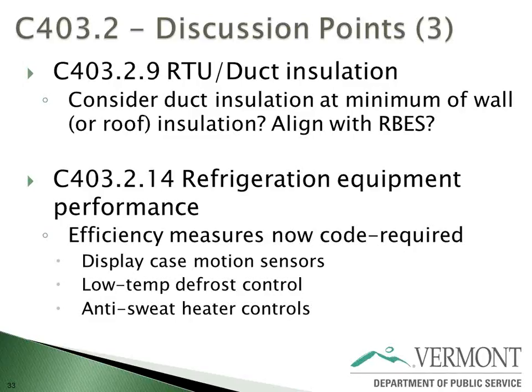beyond just manufacturer requirements, is the efficiency measures that I list here. Some of these are rebated by Efficiency Vermont right now. The motion sensors on display cases, which if you've been in a relatively updated grocery store refrigeration section, when you're the first one in there, you walk past the freezer case, the lights will come on now. That's kind of new stuff, but that's actually going to be required by code. Defrost controls for low temperature display cases, and anti-sweat heater controls that keep the frost from getting on the glass. Well, the anti-sweat heaters keep the frost off the glass. The controls keep the anti-sweat heaters from running all the time. They only run based on the humidity, the dew point of the store. So all these things are now going to be required by code, which means they're not going to be incentivized by groups like Efficiency Vermont, for good or for bad. I mean, it's basically progress towards efficiency.